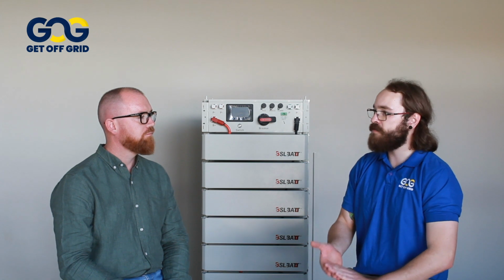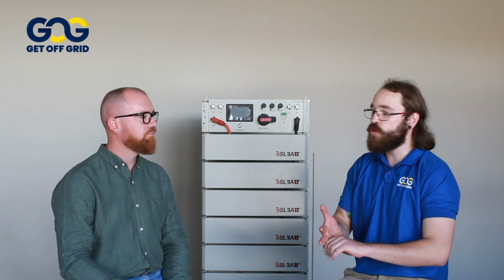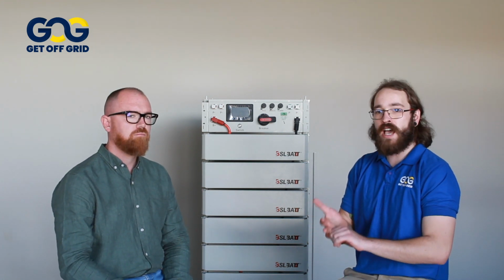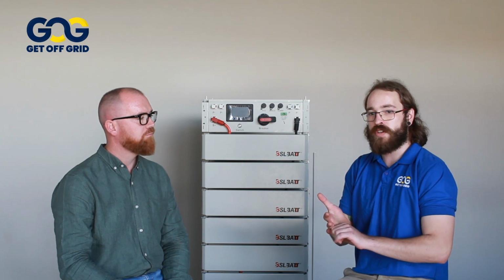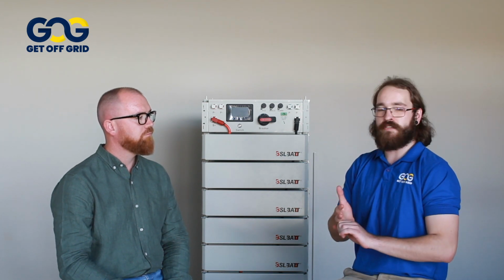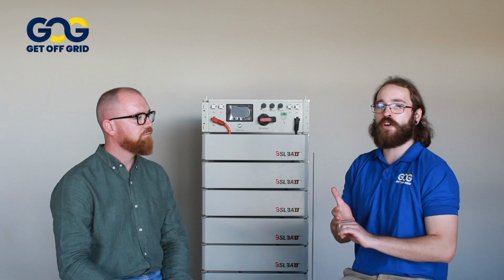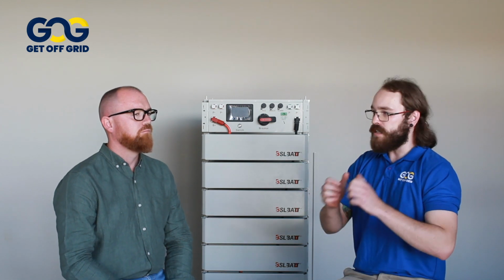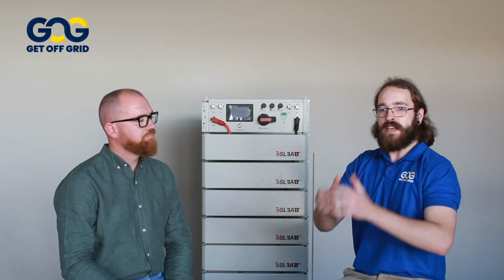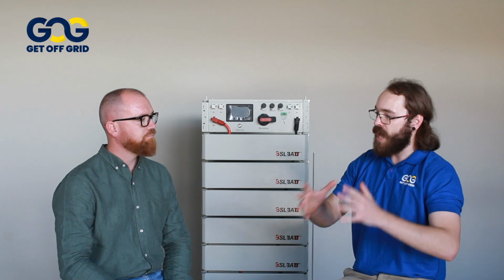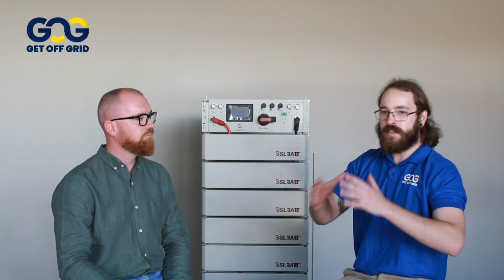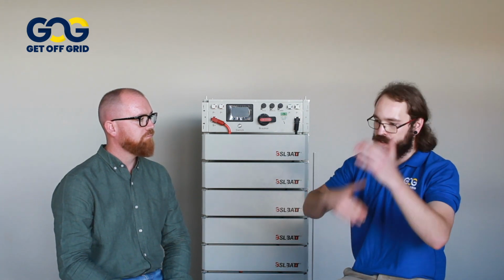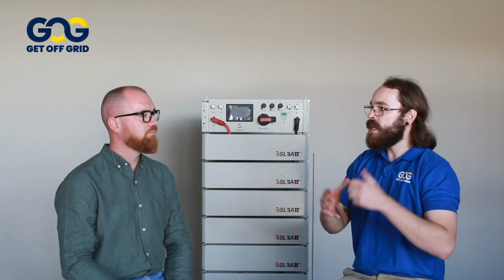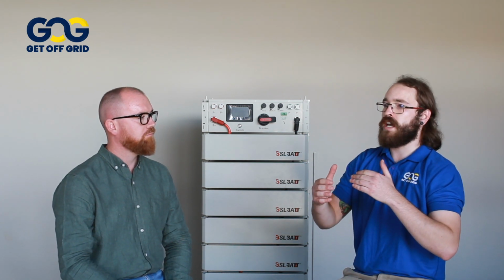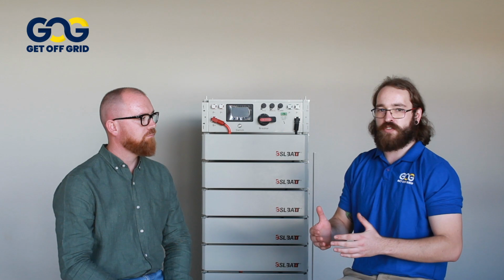There is built-in fire suppression in the form of a CO2 pack embedded inside each of the battery modules, so that if any fire or thermal runaway were to occur, the CO2 pack would detonate, forcing all oxygen outside of the battery containers, snuffing out the fire before it extends into a catastrophic failure on the battery itself.